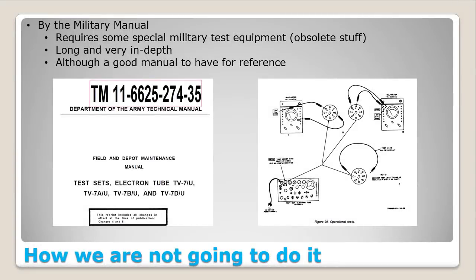All right, and this one we are titling How We Are Not Going to Do It, and that is by the military manual. You can go download this manual. It's easy to find. It does require some special military test equipment. You can see those in this picture here. It requires a couple different meters, and it's old, obsolete stuff. You would not want to go out and buy that stuff. This manual is very long and in-depth, and although it is a good manual to have because it will help you understand a little of the background on what we're doing when we're calibrating one of these things, that is not the way we're going to go. We're going to go with a much more abbreviated version.